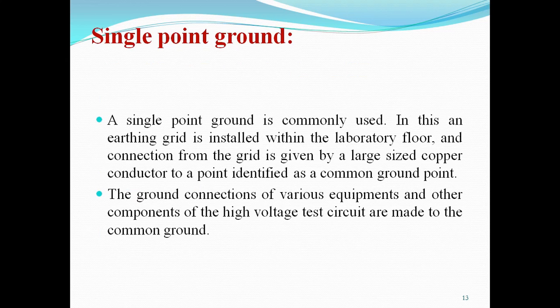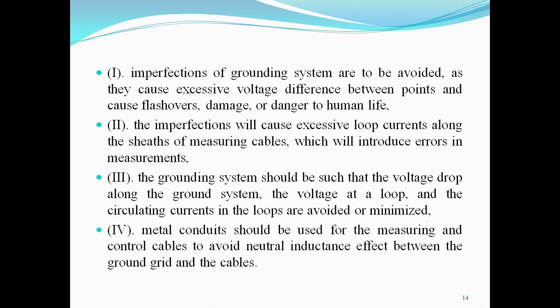Single point ground. A single point ground is commonly used. In this, an earthing grid is installed within the laboratory floor, and a connection from the grid is given by a large-sized copper conductor to a point identified as a common ground point. The ground connections of various equipment and other components of the high voltage test circuit are made to the common ground. So this kind of grounding system is also used in the high voltage laboratory. Imperfections of the grounding system are to be avoided, as they cause excessive voltage differences between points and cause flashovers, damage or danger to human life.